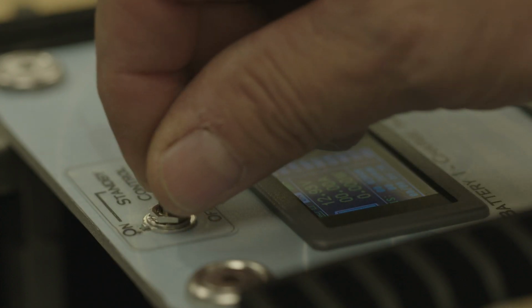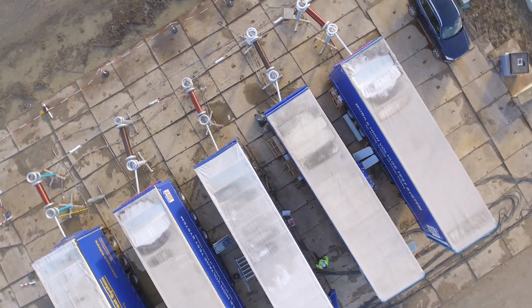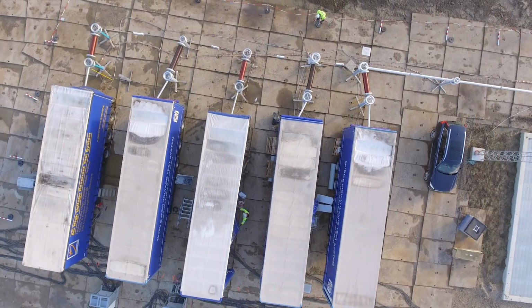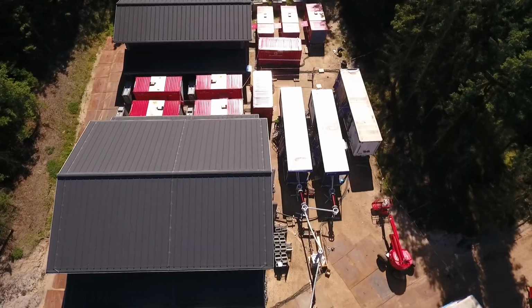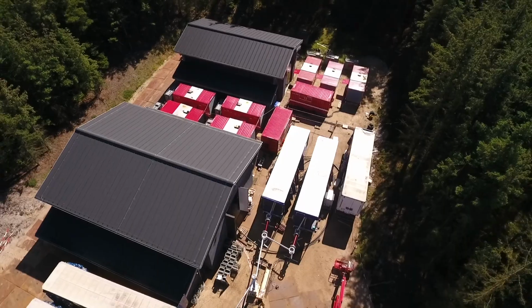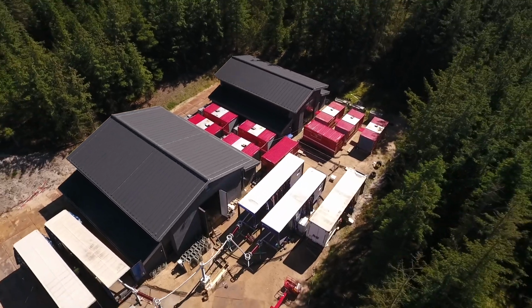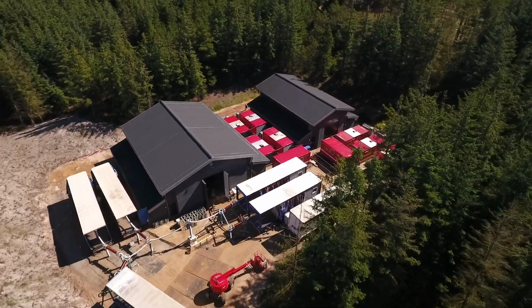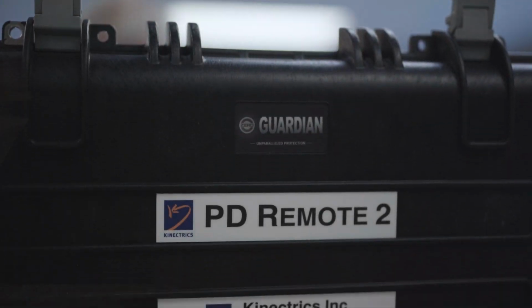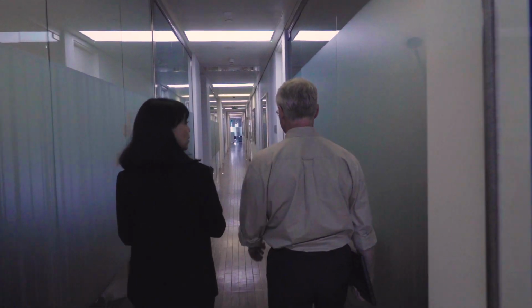We have tested some of the longest cables in the world. We have the most effective way of testing, combining the RTS testing with the daisy chain system and partial discharge system, to be able to test one of the longest cables with the most joints and be able to real-time measure the PD activity on each one of those joints simultaneously during testing.